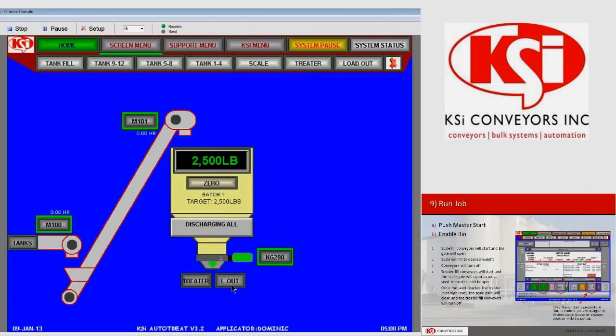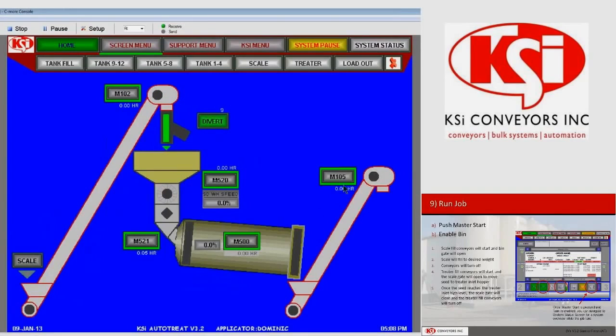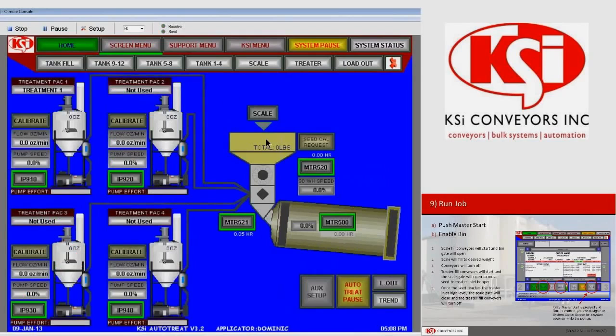So now the loadout conveyors have turned on because we had auto loadout enabled. So if we go to our loadout page, we can see that they're running. Or I'm sorry, not both, just our treater fill conveyor is running. Our treater loadout conveyor is waiting for the drum to turn on before it turns on. So right now the seed is being carried to the treater inlet. We'll navigate to our treater page so we can see what's happening. We will give a low level to the treater.